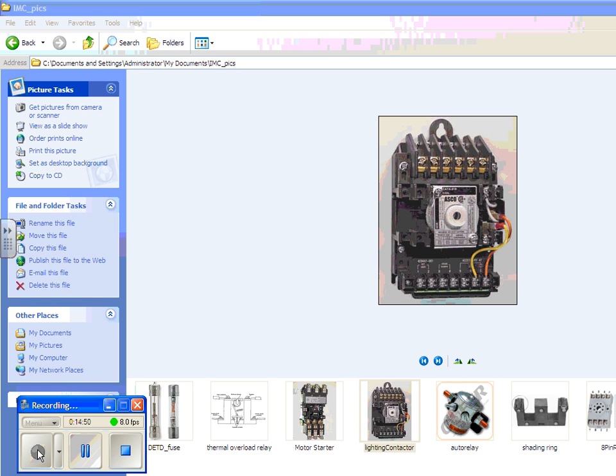Okay, the next kind of thing we want to talk about is just a simple contactor. When we say simple contactor, that relay that you start your car with is a simple relay. Well, that's true, but a contactor generally refers to where we have a lot of contacts. You'll notice that we have 7 sets of contacts, 14 sets of contacts. There's no holding contact, or is there? This might have a holding contact, but it's still just a lighting contactor, because what do we not see on this thing? Overload relays. It's not intended for motor use, right? This is for maybe parking lot lights where you want to turn on 7 circuits or 14 circuits of lights, and you want them turned on all at once, like when it gets dark. So this is a lighting contactor.